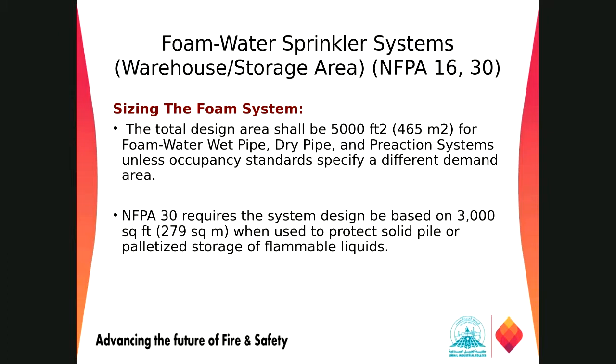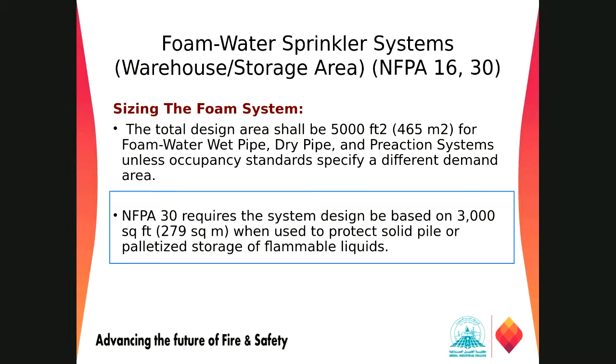So the total design area shall be 5,000 square feet for foam water wet, dry, and pre-action systems, right? And NFPA 30 requires 3,000 square feet when used to protect solid pile or palletized storage of flammable liquid. So we have requirements from NFPA 16 and from NFPA 30.